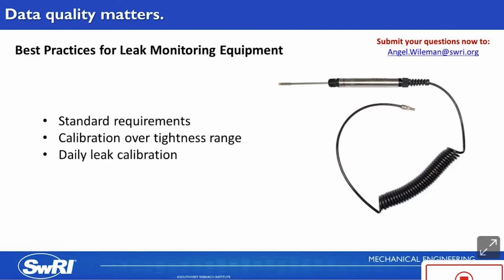The standards also require daily leak calibrations of the mass spectrometer or the methane detector with a calibrated leak. Typically, you can get calibrated leak standards with a valid calibration certificate from the rental company of the gas detector. And make sure you keep a record of these daily calibrations.